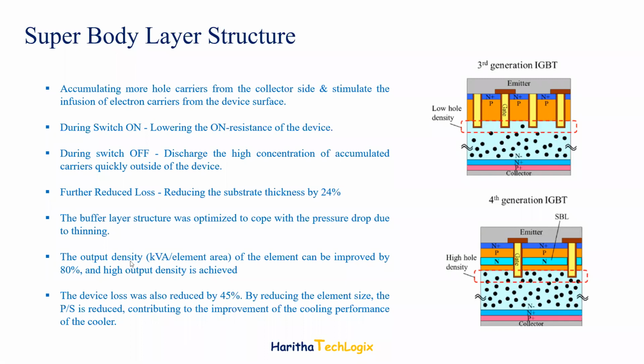You can see the output density of the element, the kilovolt-ampere per element area, has been improved by nearly 80%. It's such a huge improvement, and overall high output density is achieved, and the device loss has been reduced by 45% by reducing the element size. The power stack has also been reduced overall to contribute to improved cooling performance.